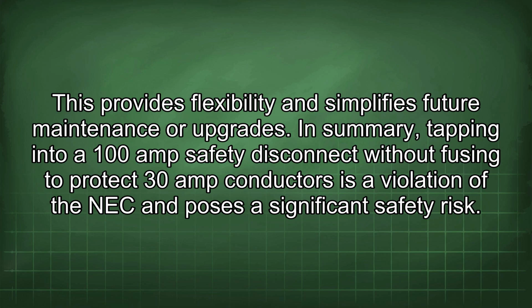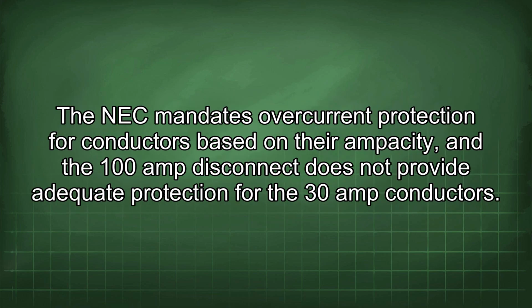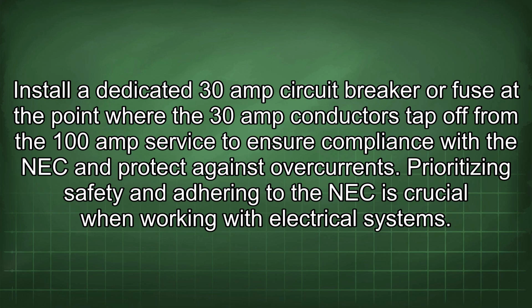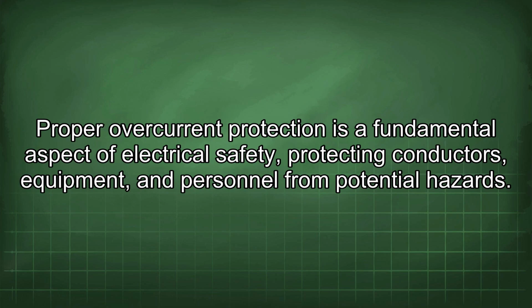In summary, tapping into a 100 amp safety disconnect without fusing to protect 30 amp conductors is a violation of the NEC and poses a significant safety risk. The NEC mandates overcurrent protection for conductors based on their ampacity, and the 100 amp disconnect does not provide adequate protection for the 30 amp conductors. Install a dedicated 30 amp circuit breaker or fuse at the point where the 30 amp conductors tap off from the 100 amp service to ensure compliance with the NEC and protect against overcurrents. Prioritizing safety and adhering to the NEC is crucial when working with electrical systems. Proper overcurrent protection is a fundamental aspect of electrical safety, protecting conductors, equipment, and personnel from potential hazards.